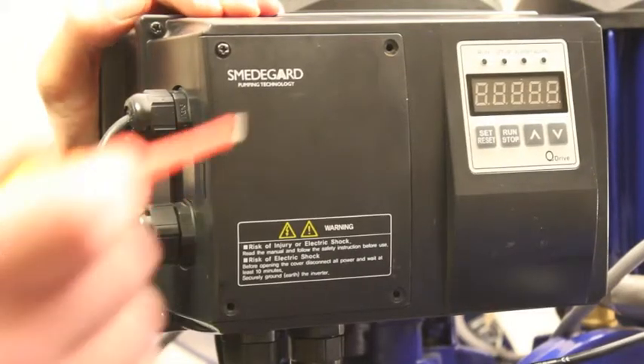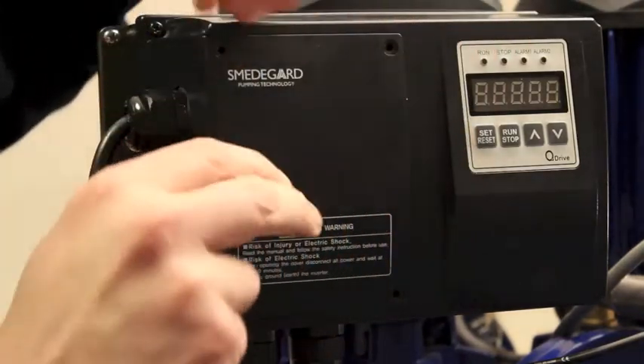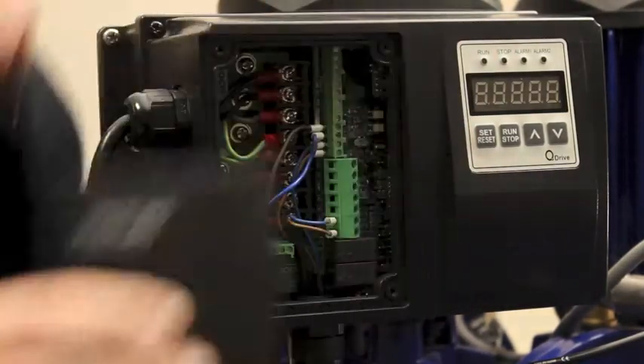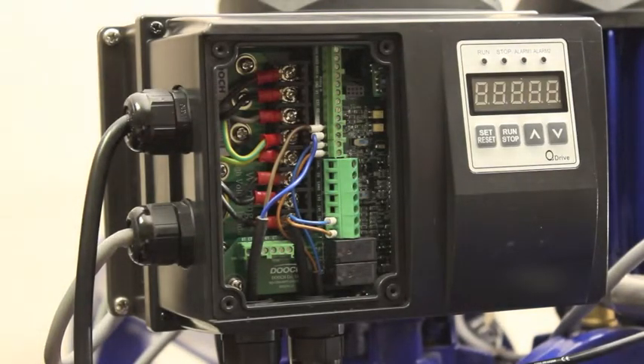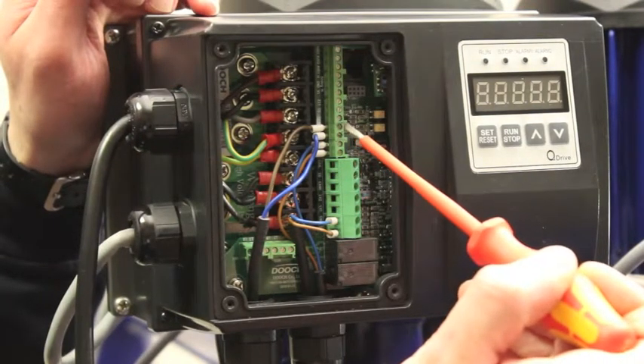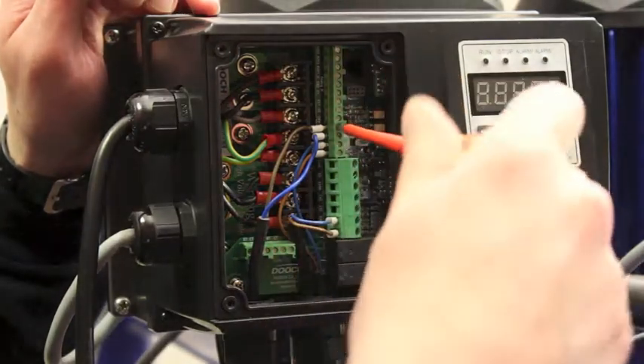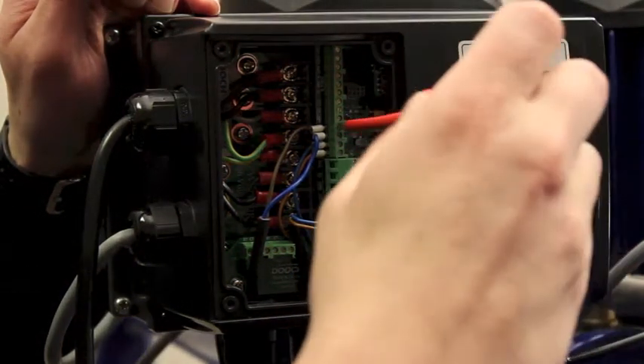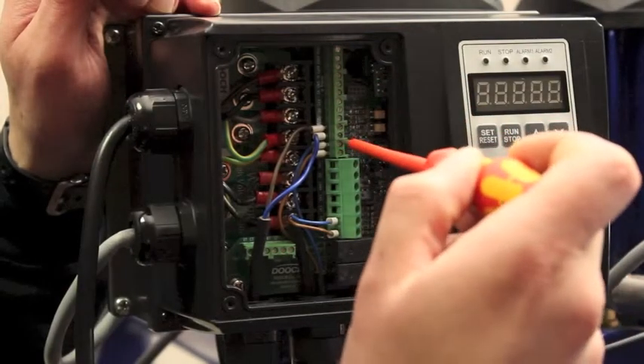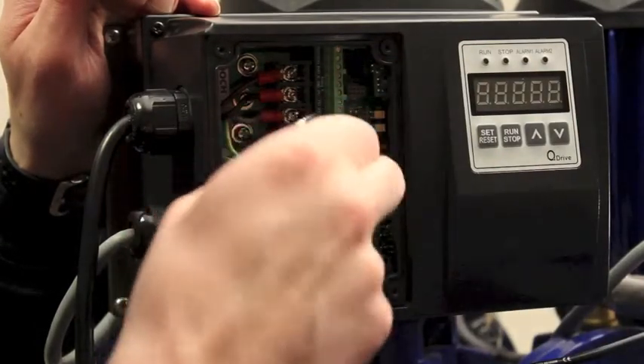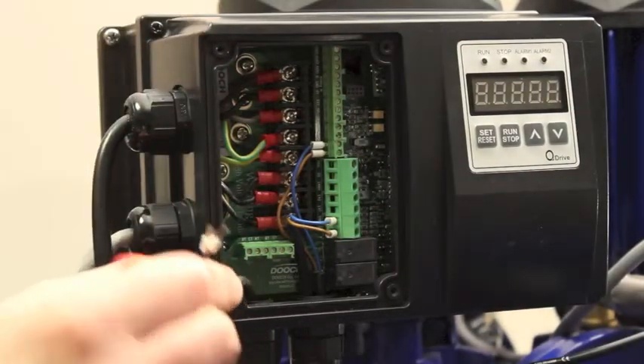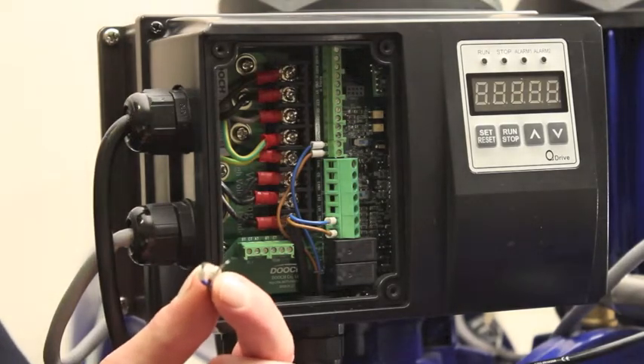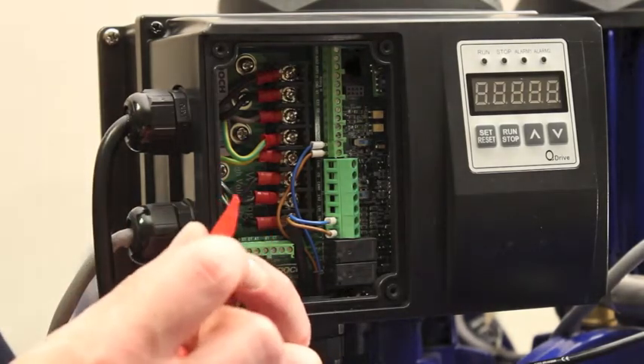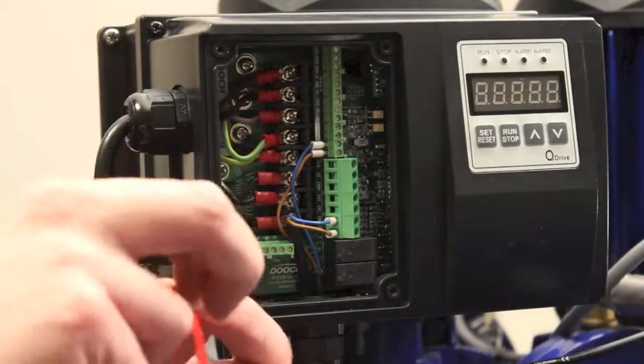Remove the terminal cover fixing screws and lever the cover off from the left hand side. Remove the wires from either P1 and CG terminals or Run and CG terminals. After removing any wires and making them safe so they cannot touch anything, replace the cover and reinstate the power to the Q Drive.